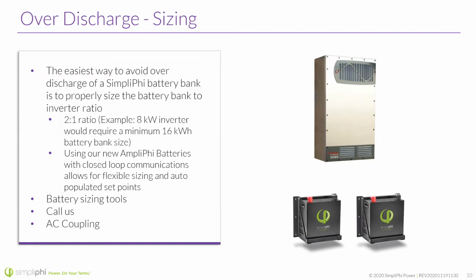AC coupling, I leave that little mark there as it's always important to talk about. Well, actually, we'll leave that out for charging, but I'll come back to it. AC coupling does make things a little different. This ratio is really important when it comes to AC coupling on both the inverter side and the PV side, meaning the PV should be the 1 and the battery be the 2. So same kind of deal as the inverter. And I'll talk a little bit more about that later on.